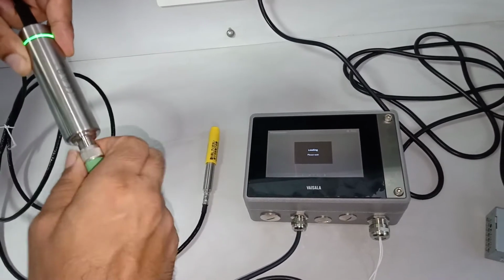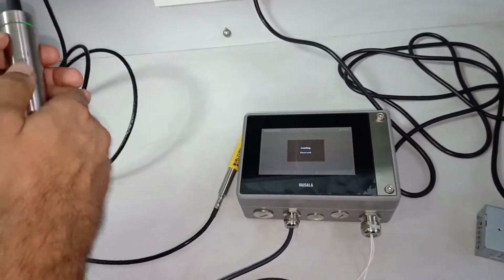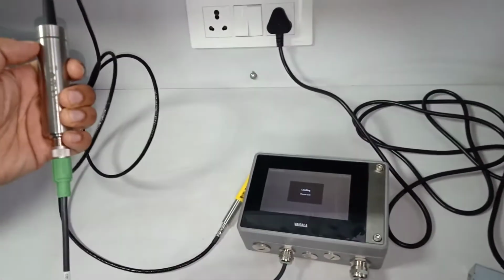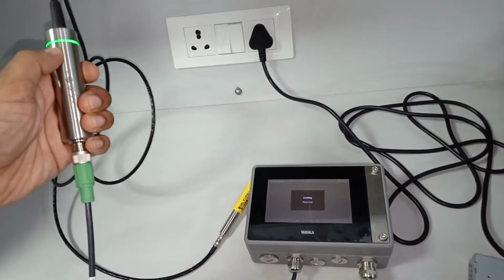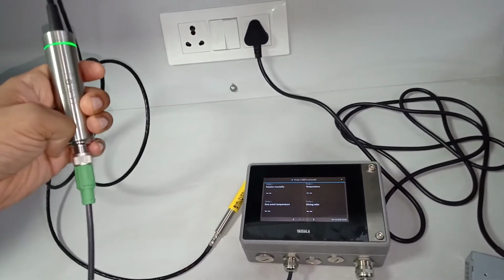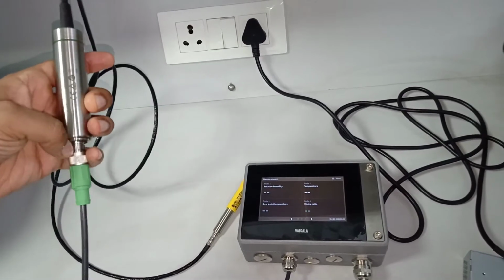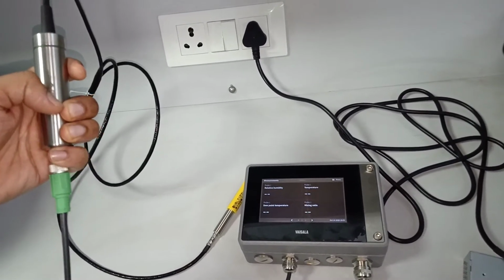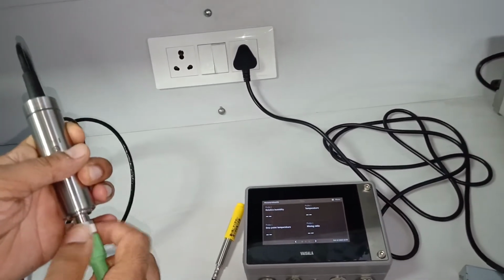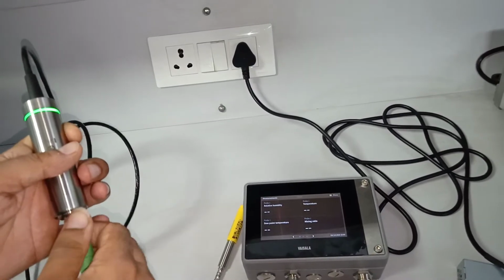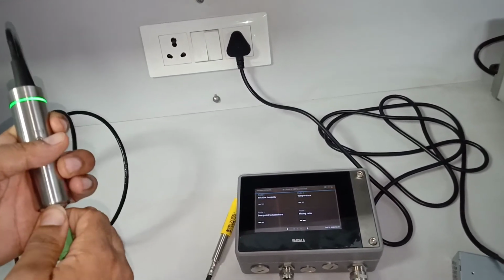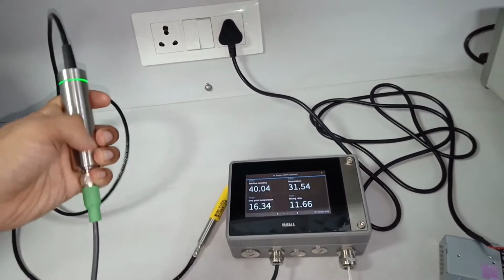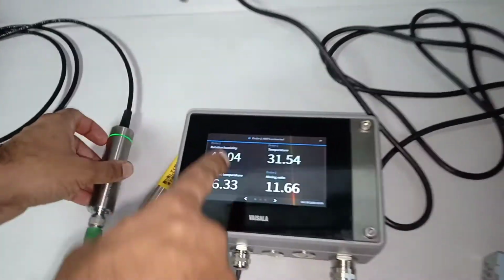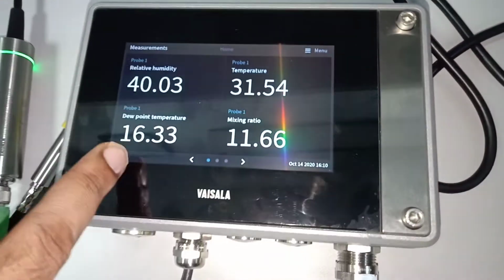So this is also a very nice feature. So yeah, from some distance you can see whether the probe is working well or not. So the green blinking signal shows that the readings are fine and there is no malfunction. But as soon as you get the red, then there is some problem in the probe or maybe some malfunction. So it has been configured for relative humidity and temperature.